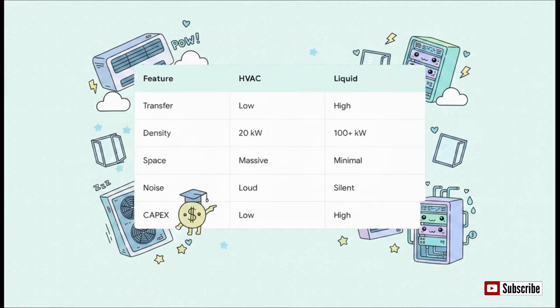When we put legacy HVAC head-to-head with next-gen liquid cooling, the trade-offs are pretty undeniable. Liquid dominates in heat transfer and silent operation, and allows incredibly dense AI racks shoved into very small physical spaces. Legacy air, on the other hand, requires massive, sprawling rooms, complex raised floors, high ceilings, and creates deafening noise from thousands of spinning fans.